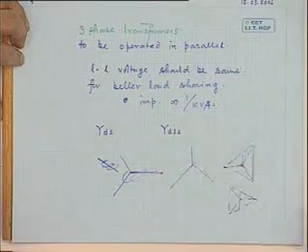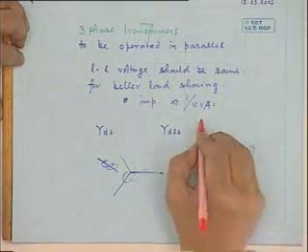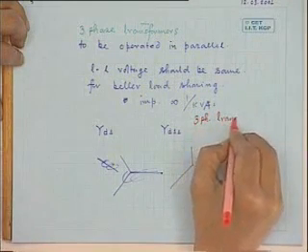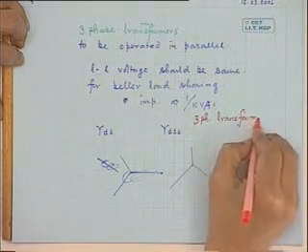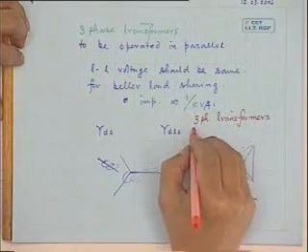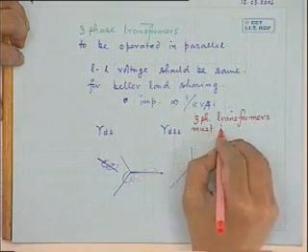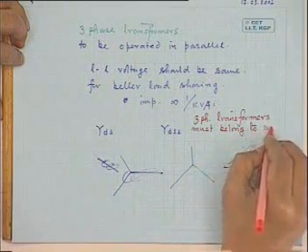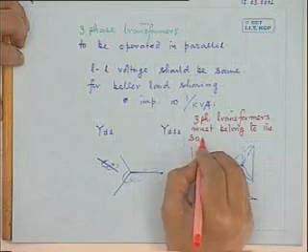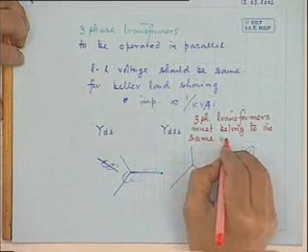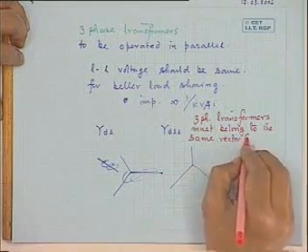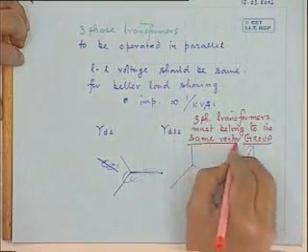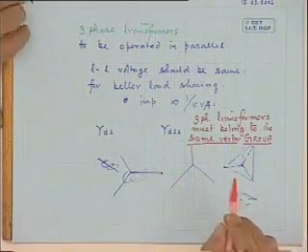That is, the three-phase transformers must belong to the same vector group. This is very important.